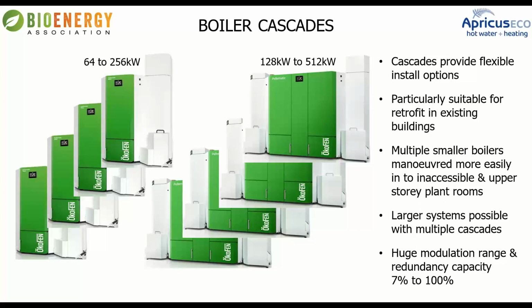And then you just cascade the boilers to have a bigger system. And you've got a really massive modulation range with a cascade. So, for example, with the 512 kilowatts, a 0.5 megawatt, which is a significant amount of energy, we've got a modulation range from 7% of peak output to 100% of peak output. So that means it's extremely efficient to run, because it's going to run based on what is the current load. So in the middle of winter, if you need a 0.5 megawatt, great, they're going to go full noise and provide that. But then if you're doing domestic hot water and it's a warm summer's day and the water's already quite warm coming in, and you only need really to add a little bit of energy, it will go down as low as 36 kilowatts. So no bother or fuss at all for the boiler. It's not going to change anything. It's just going to make sure that they're performing at absolute ultimate efficiency all the time.